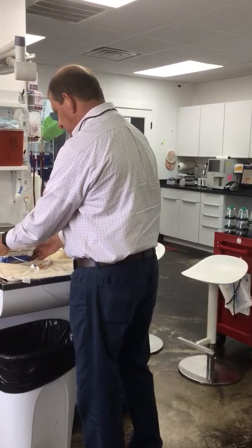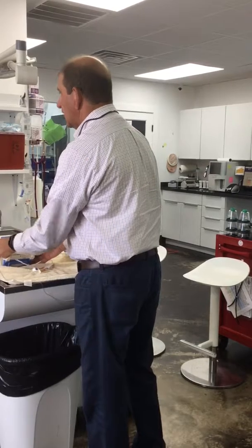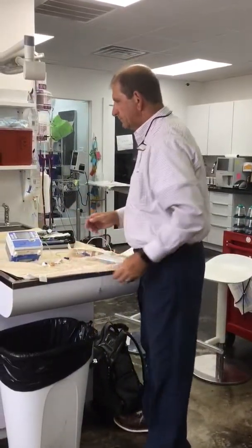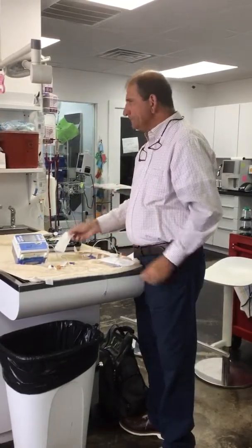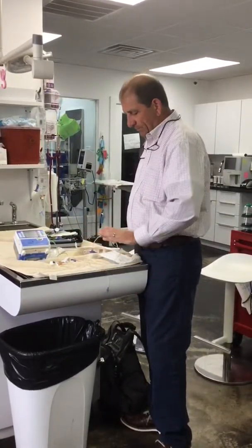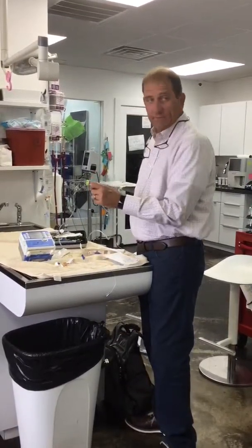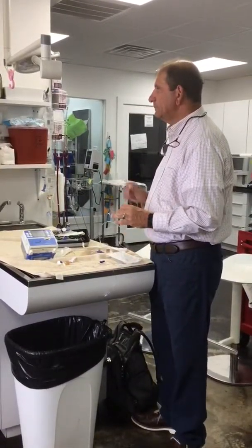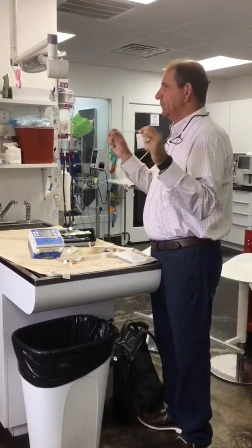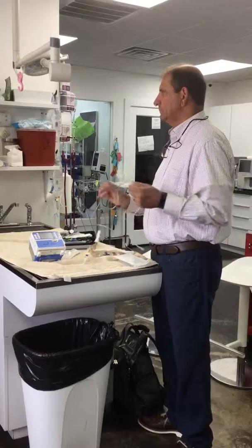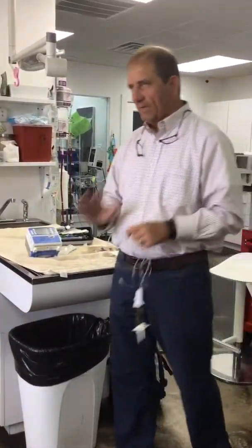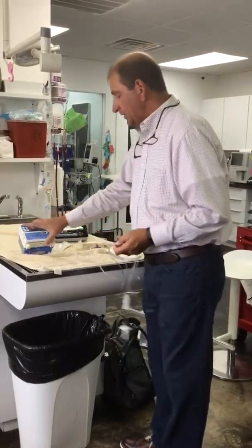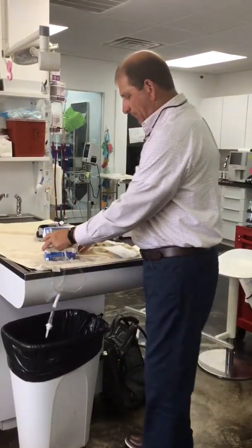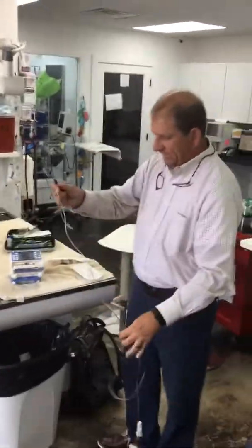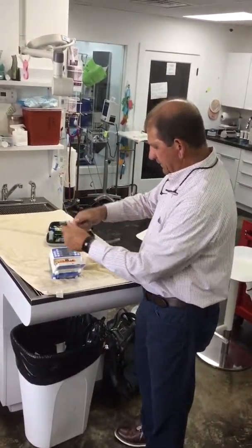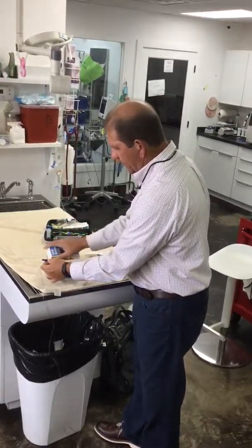Show it later. No, hold on one second. Sorry, we don't carry those. We use 2 different kinds, but we don't have an example of one of them. We have the micro bore, and then we have a macro bore, which is usually a 7.6 mil prime. You're gonna have some of these for stuff like that. And you will then calibrate that. This is gonna be the same calibration, because we're gonna do it in a 10 drop. I got you. Great. Don't worry about calibration. I'll make sure you guys are correct. I promise. So if I wanted to do a syringe infusion, I'm gonna open it up and I'm gonna put this tubing in there. Now the thing you gotta do is, this connector has got to be on the pump side.